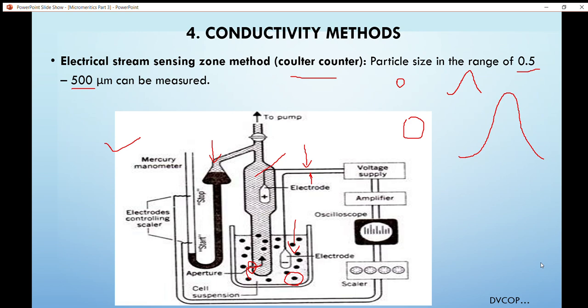The pump draws a known, fixed volume of electrolyte from the outer solution to the inside of the glass tube through a small orifice. During this movement, suspended particles also pass through the orifice, which is constructed so that only one particle passes at a time. When a particle enters the orifice, it displaces its own volume of electrolyte, causing a short-time change in resistance across the orifice. This voltage change produces a corresponding change in signal on the analyzer.